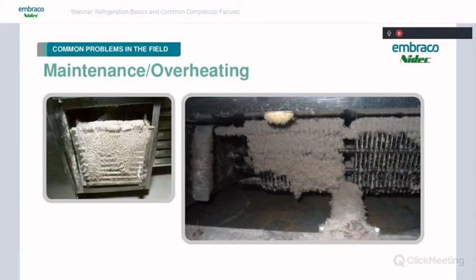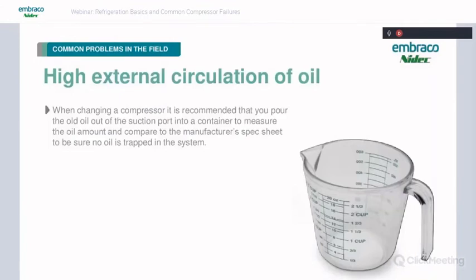And if it gets too bad and it runs like this for too long, it may not trip the overload. And then the technician finally goes in there and he cleans all this up, and you've degraded your oil so bad that it broke down and clogged up the cap tube. So obviously, very important to do a good job of maintaining this equipment. Keep the coils cleaned and this and that.